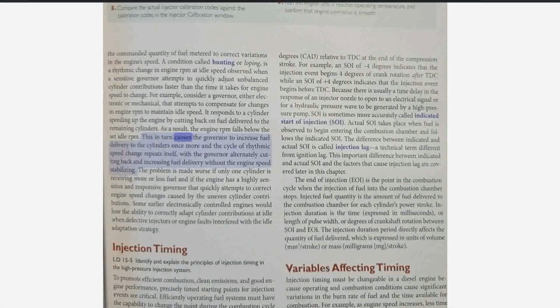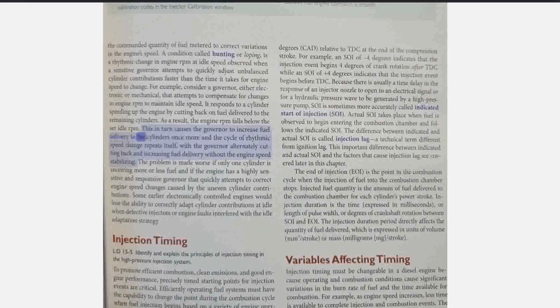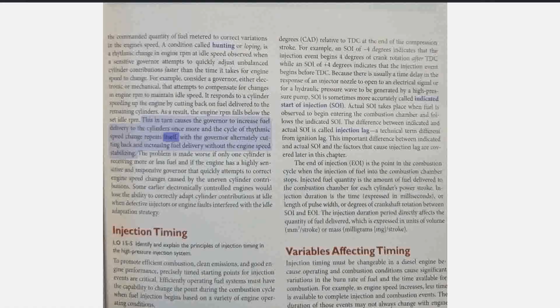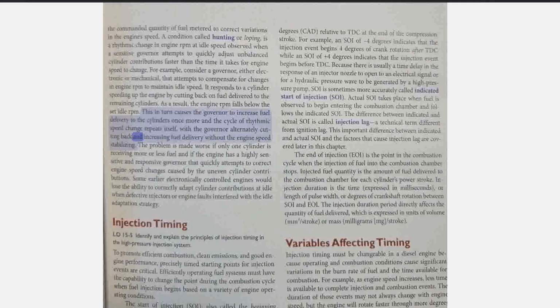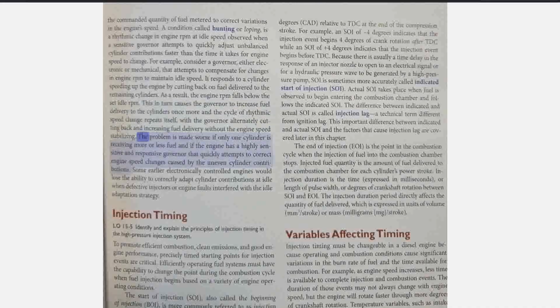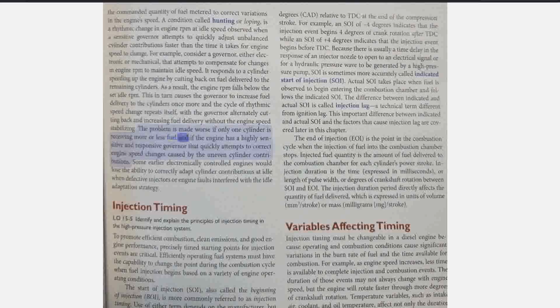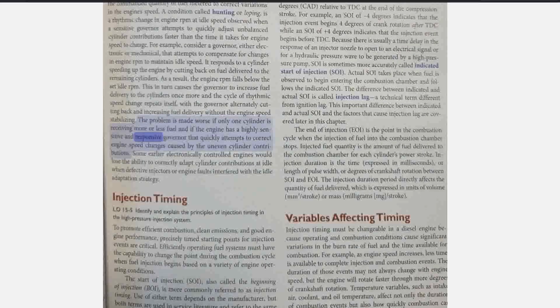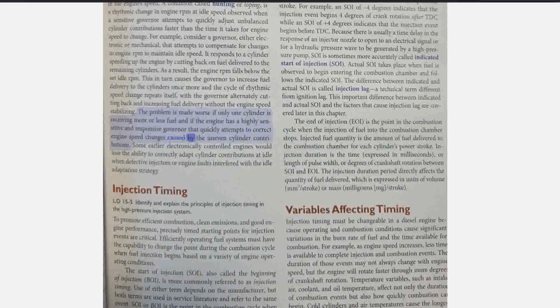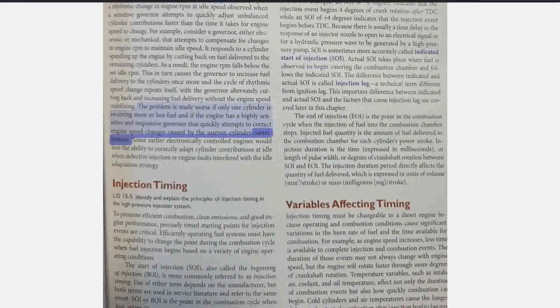This in turn causes the governor to increase fuel delivery to the cylinders once more, and the cycle of rhythmic speed change repeats itself, with the governor alternately cutting back and increasing fuel delivery without the engine speed stabilizing. The problem is made worse if only one cylinder is receiving more or less fuel, and if the engine has a highly sensitive and responsive governor that quickly attempts to correct engine speed changes caused by the uneven cylinder contributions.